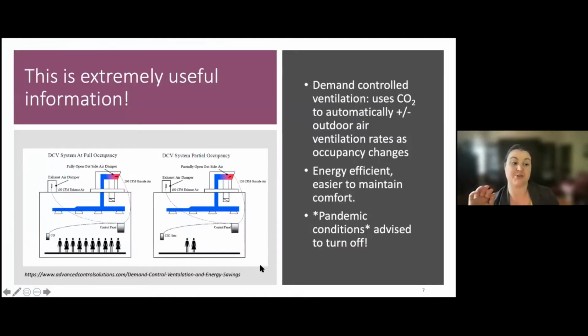This is extremely useful information and can be used in a variety of ways. In research, CO2 monitors and levels are often used to estimate ventilation in a space—just to understand how much fresh air is actually coming in. But CO2 monitors can also be used in specific applications like demand controlled ventilation, which uses indoor CO2 levels to automatically increase or decrease fresh outdoor airflow depending on occupancy.